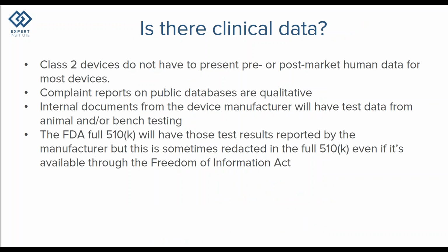Unlike drugs, and unlike very high-risk devices, most medical devices that are sold in the US do not have to go through a clinical trial, which means that if you're looking for public information on the FDA's website, you are most likely not going to find any formal clinical trial data on human beings.